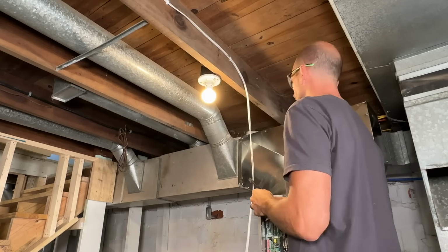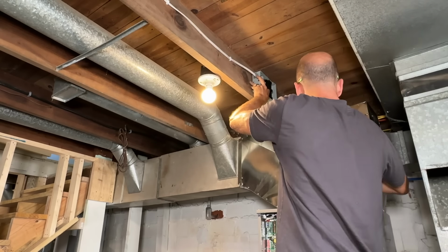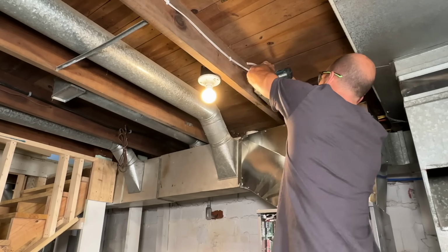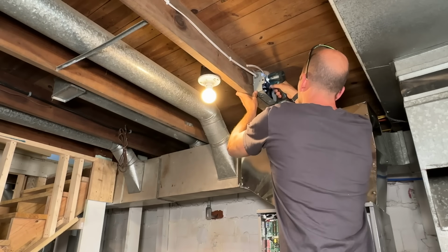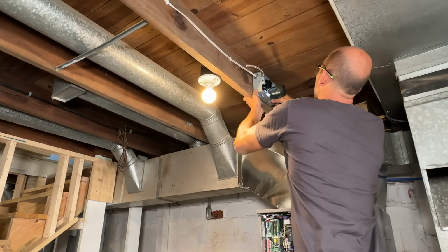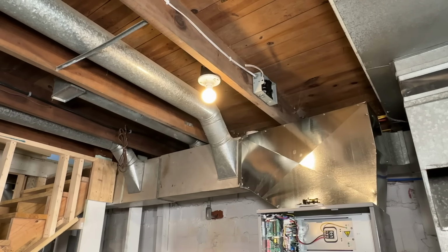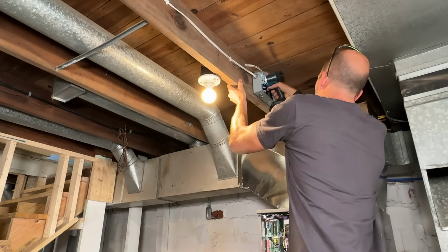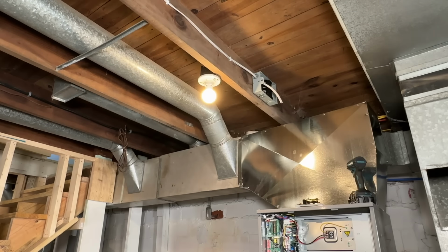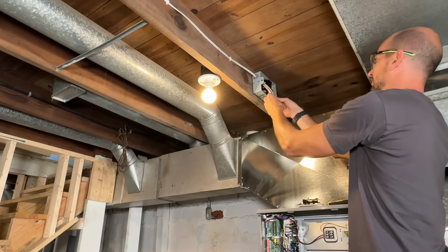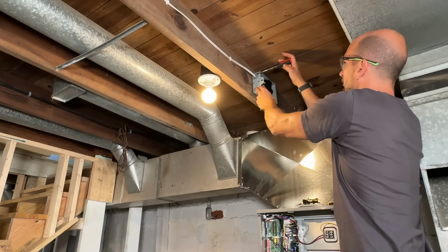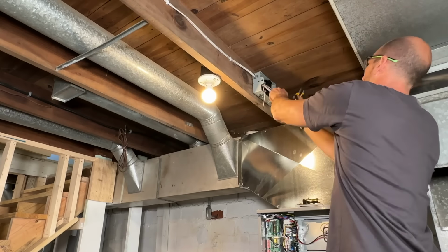Now, since it's a 240 volt circuit, by code, we do need a disconnect method at the actual unit. So I'm putting another 30 amp disconnect here inside, which will connect the 14-2 and then run some protected wire down to the unit itself, not just running Romex down to the unit.